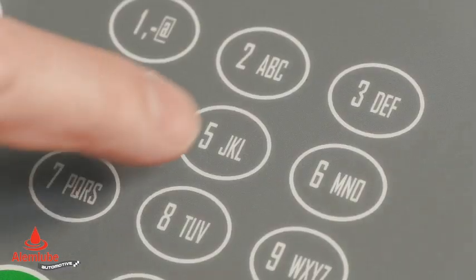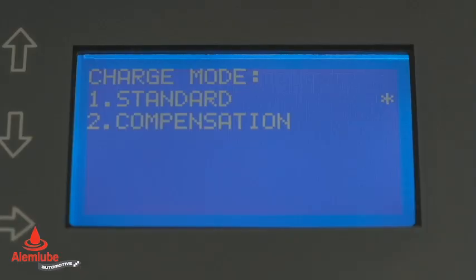By typing 5 it is finally possible to set the charging mode. By default, selection 1, standard mode is set. In this mode, at the end of the charge, it is necessary to turn on the vehicle's air conditioning system and have the residual gas present in the pipes aspirated from the low pressure side.